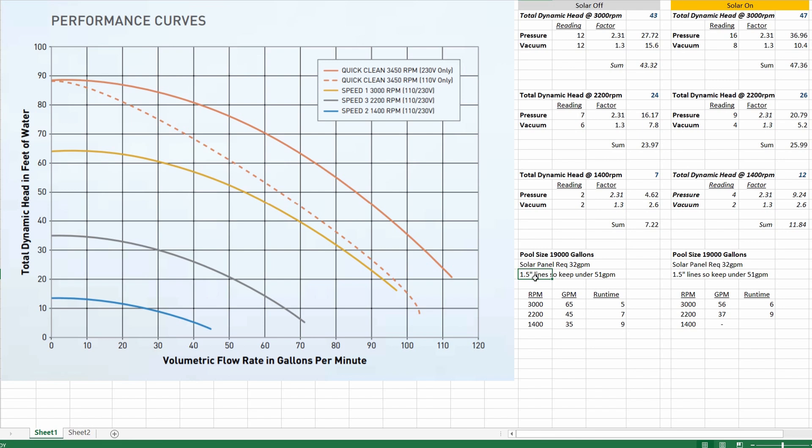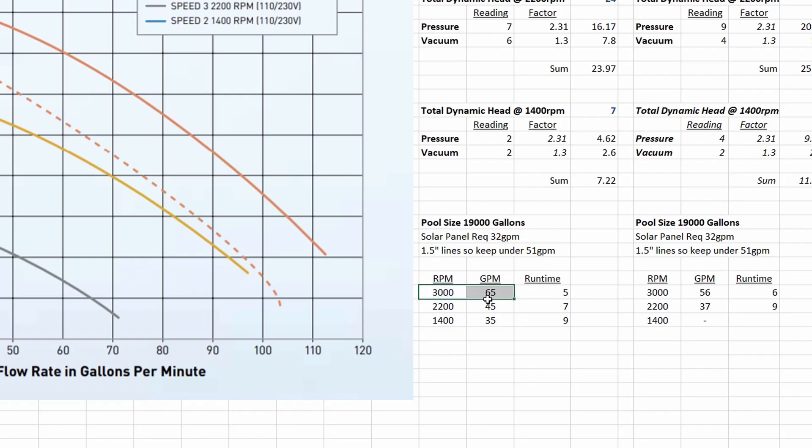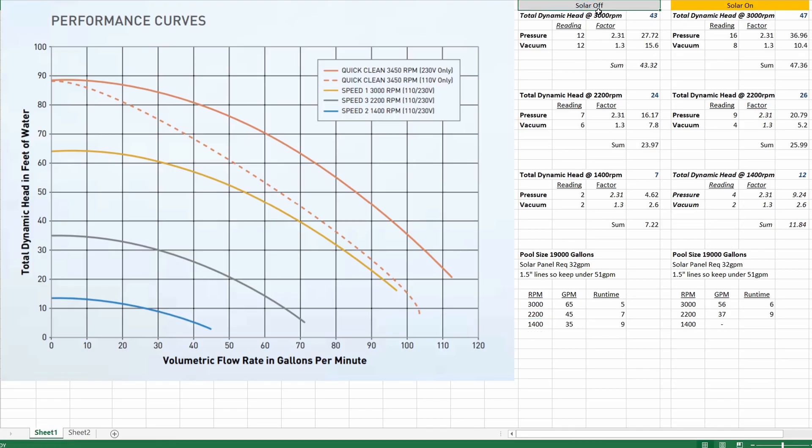So running at 3000 RPMs would be overkill because that would give me 65 gallons per minute. 2200 RPMs would work out at 45 gallons per minute and so would 1400 RPMs but all these readings were taken with the solar off.